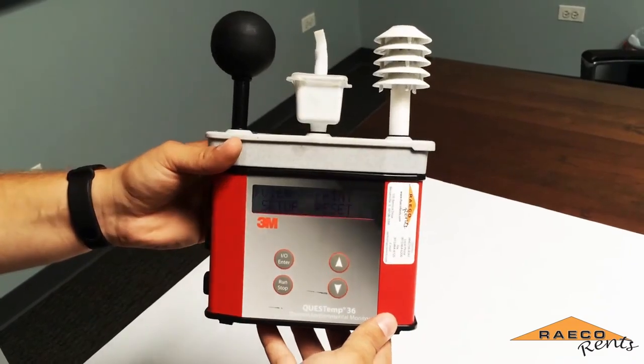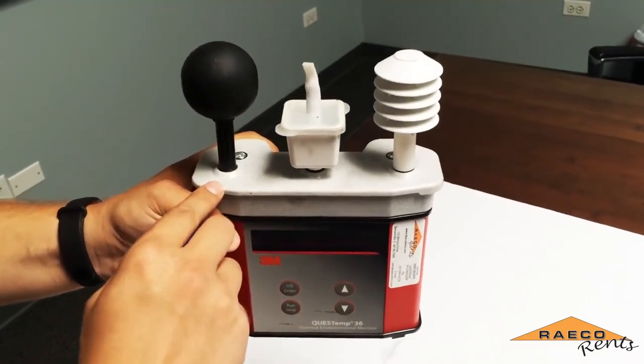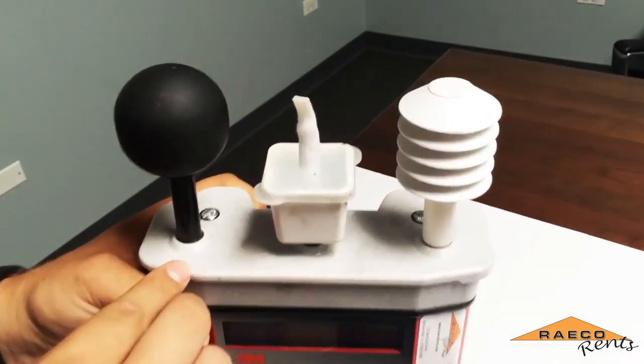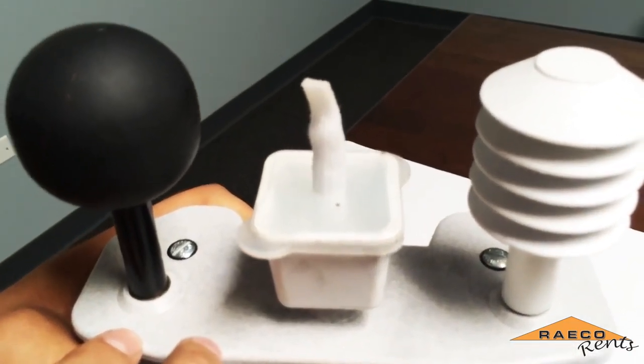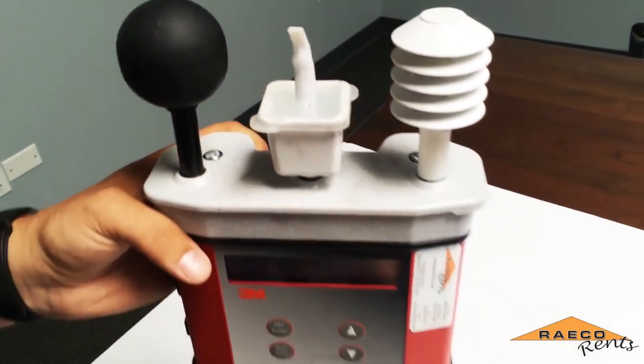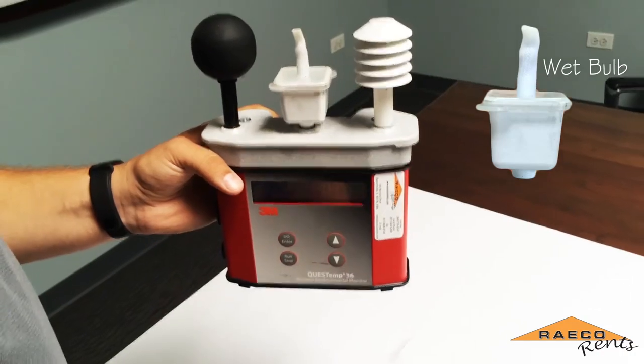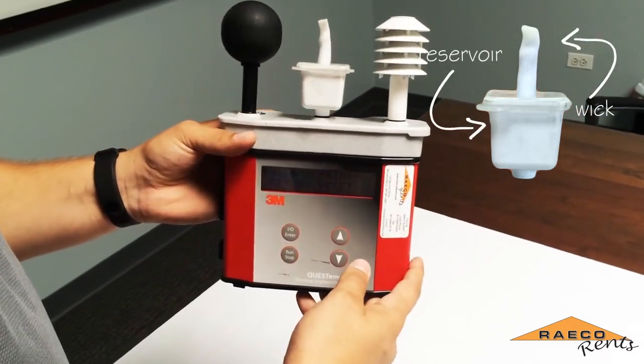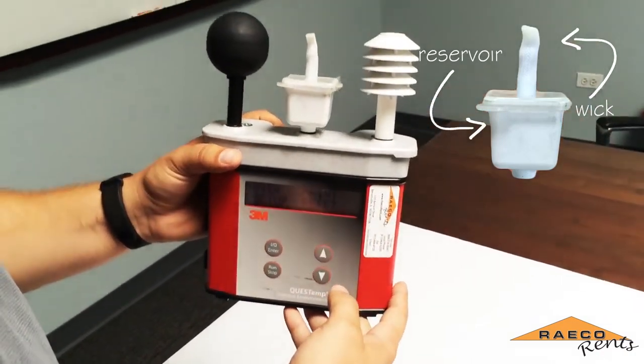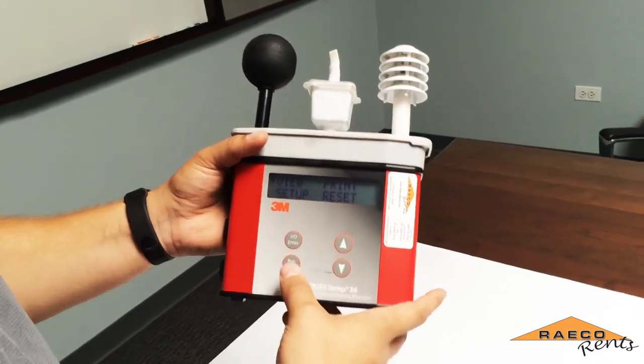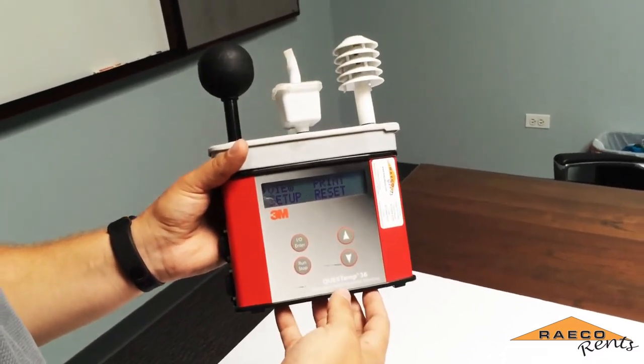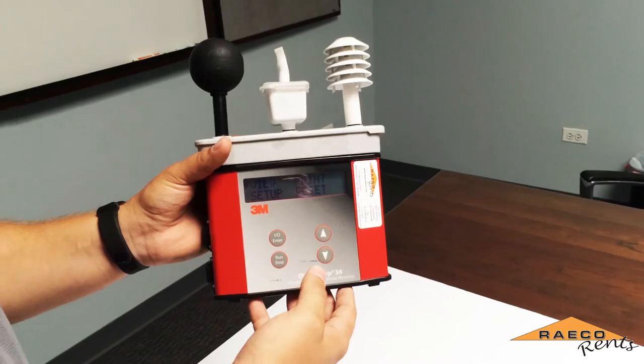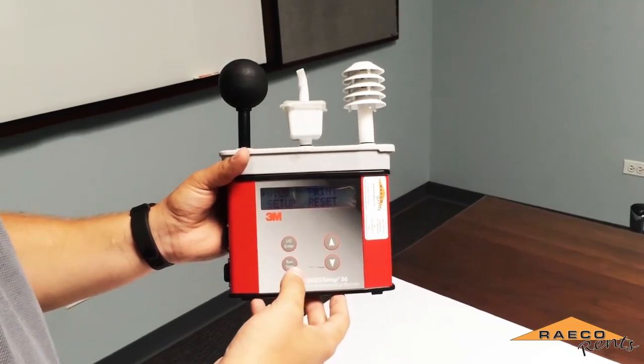test. First thing you want to do is check whether the wet bulb wick is clean and whether the reservoir is filled with water. If it isn't, you want to fill it with deionized or distilled water in order to keep the wick clean longer. You want to keep the QUESTemp in a safe area, roughly 3.5 feet off the ground.